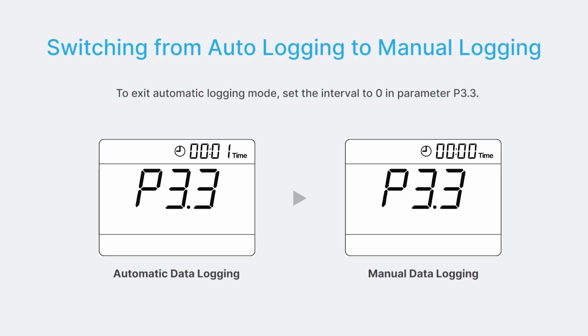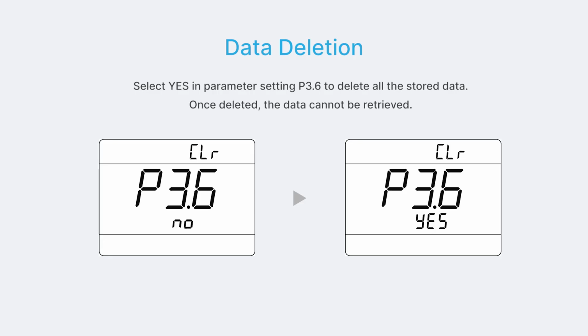To exit automatic logging mode, set the interval to 0 in parameter P3.3. Select Yes in parameter setting P3.6 to delete all the stored data. Once deleted, the data cannot be retrieved.